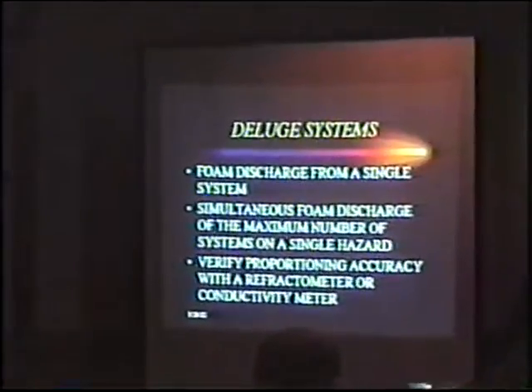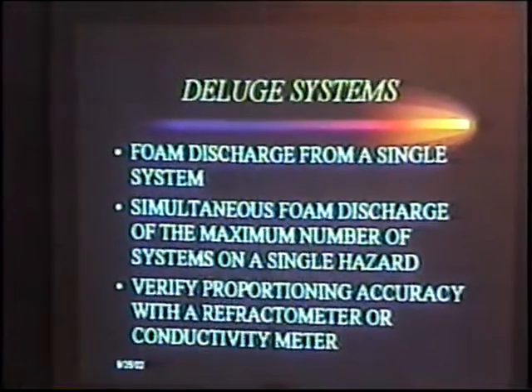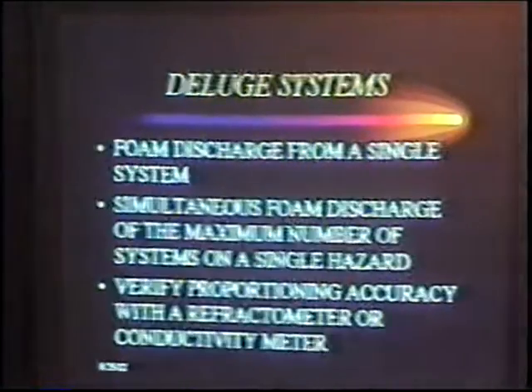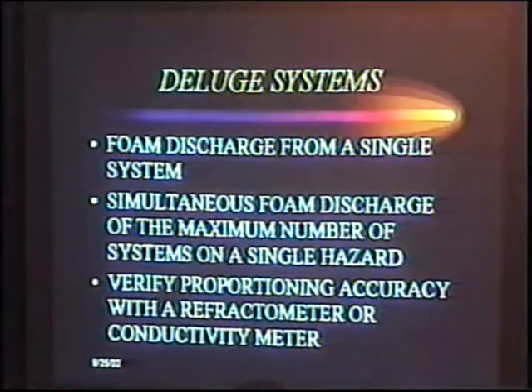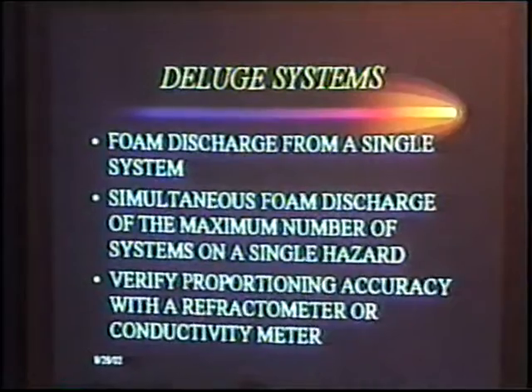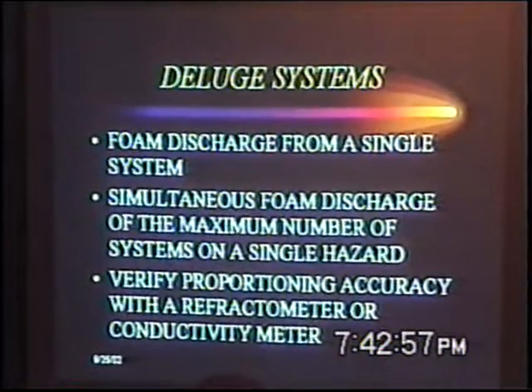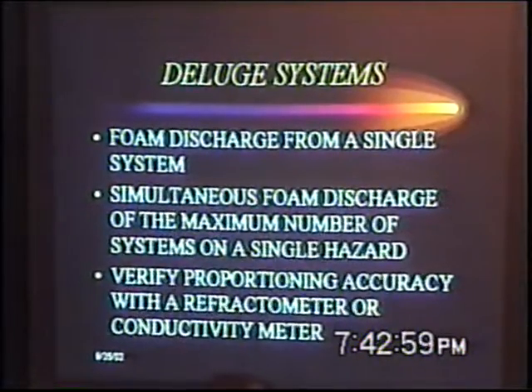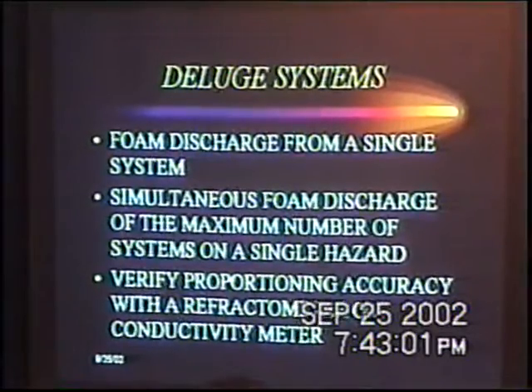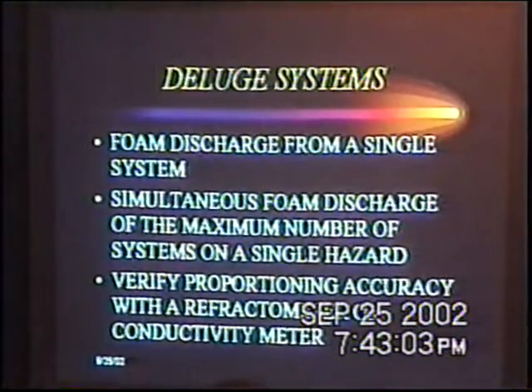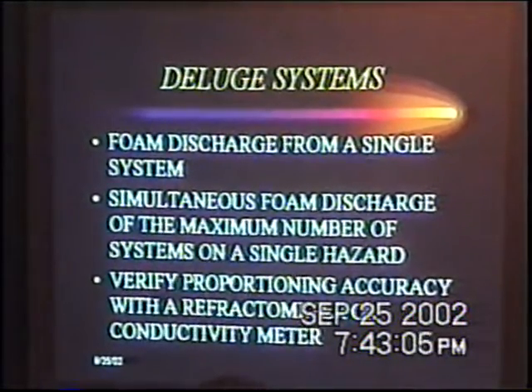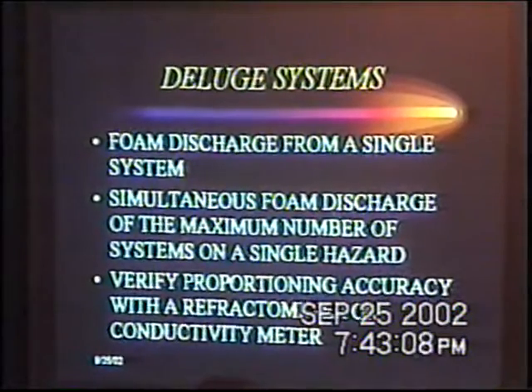If you're testing a deluge system, typically what NFPA 16 requires is that you first test from the single system. If you only have a single system, that's all you worry about. But if you have multiple systems, then you have to have a simultaneous discharge of the maximum number of hazards. So like if we do an airplane hangar, you might just test a single zone, and depending on the size of the hangar, you might have a total of three zones at maximum. And so you would dump the whole zone.